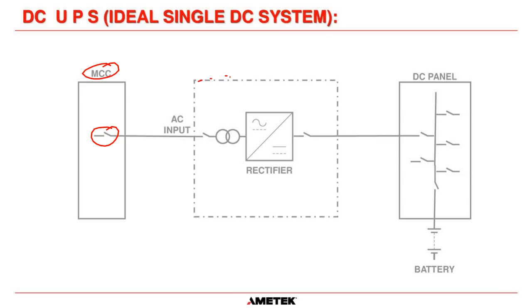But the difference that you can see on this drawing compared to the last drawing is the way that we connect the battery and the loads at the DC panel. You can see here that the battery is now connected at the DC panel. You can either have a breaker here onto the main bus, or in some really critical operations, I think there's a drawing for that later on, where you'll see where the battery is connected without a breaker, if you don't want there to be a single point of failure between the battery and the loads themselves.